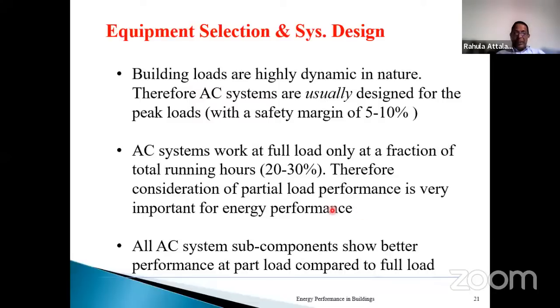And the cooling load, well, once we fix an equipment to a particular load, we see that very rarely it will run at the full load condition. Most of the time, 70 to 80% of the time, it will be outside the full load condition. So therefore, equipment will always operate at the part load condition. This is a very important thing.